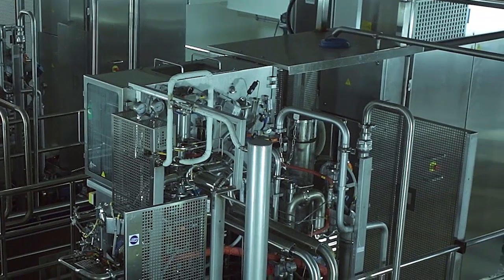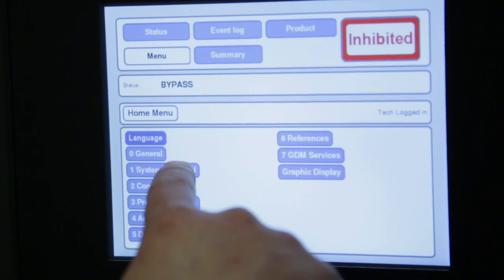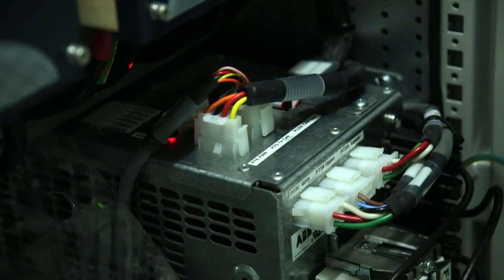The background for the project was that we process a large amount of UHT milk, and that requires us to maintain a high level of sterility in the plant. Whenever we have a power event — which is often triggered by events outside our site — we lose that sterility to the machine. Our automation systems pick up on a power glitch and therefore assume the plant will be non-sterile. It means we have to then re-clean or CIP, then go to a sterilisation step, and then we can start running product. This takes us around about four hours.